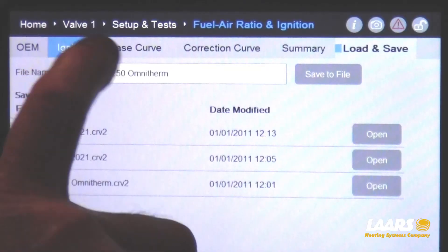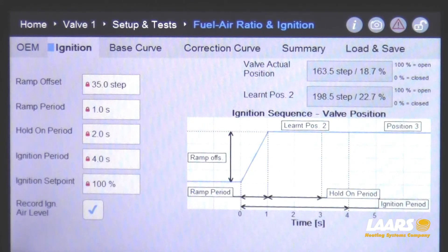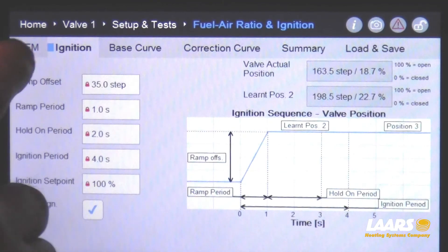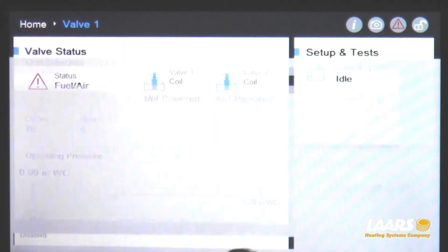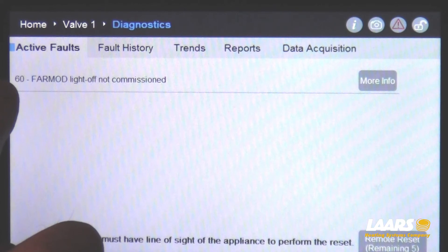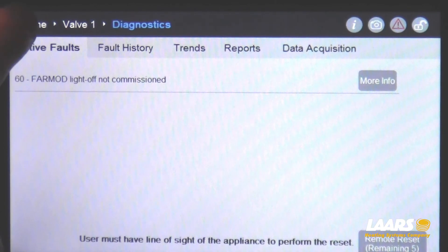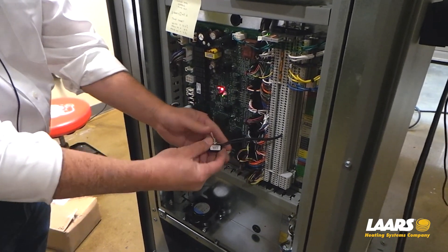Come up to ignition. Any time you change your correction curve, you have to record the new ignition air level — check mark it. However, you do have to interrupt your TT call or call for heat, then re-enable it so the boiler will acknowledge the new recorded air level. For example, I've check-marked it, and on the home screen you'll see a fault present — error code 60, which is FAR mod light-off not commissioned — because I did not interrupt my call for heat. So we'll interrupt the call for heat, give it a call for heat, and let the boiler record the new ignition air level.